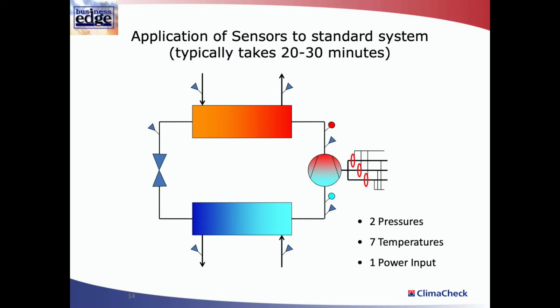The simple circuit shown here shows power input being recorded at the compressor to the right, low pressure and high pressure transducers for suction and discharge pressure, a temperature sensor for suction inlet and discharge, and also a temperature sensor just before the expansion valve. Temperature sensors are also applied to the evaporator inlet and outlet, chill water or air, and also to the condenser, condenser water or air, and these are not necessary for ClimaCheck to perform her calculations, but are very, very important to determine whether or not there are inadequate flow or excess flow characteristics at these secondary points.